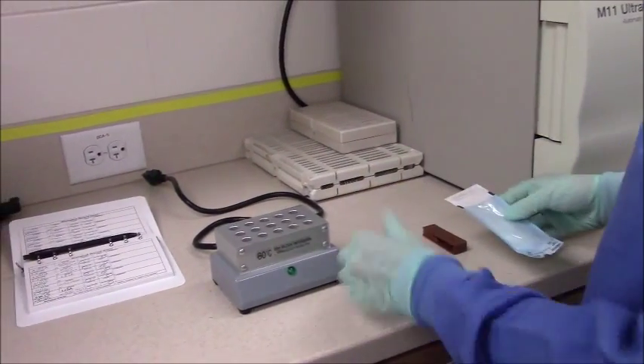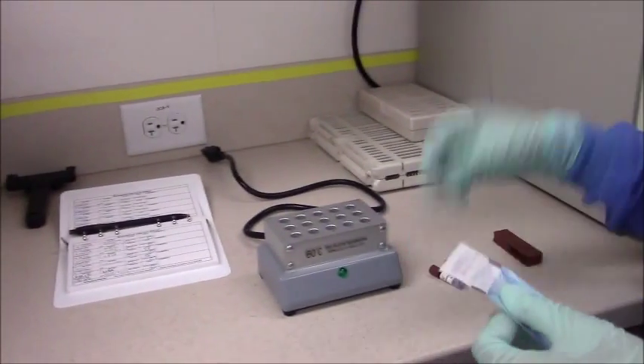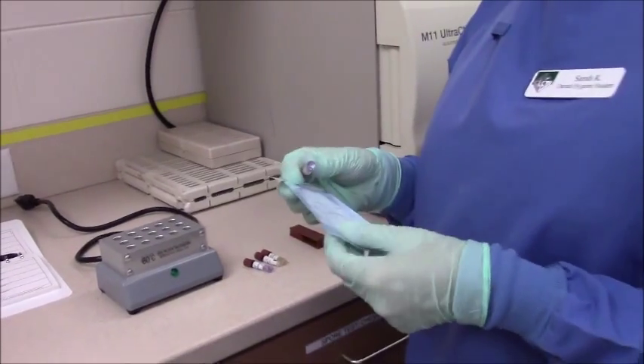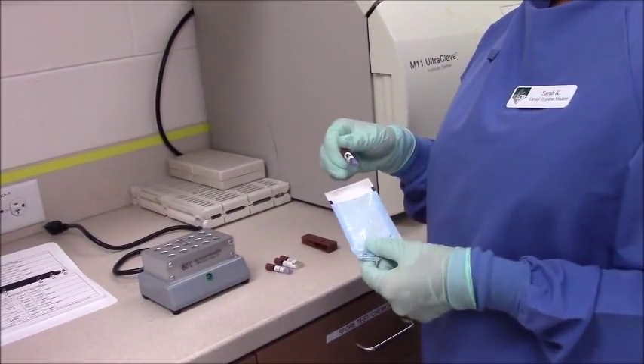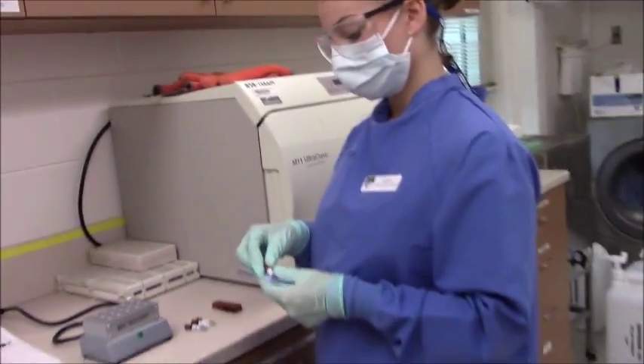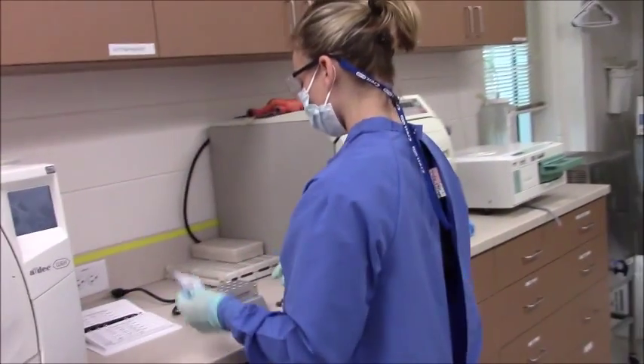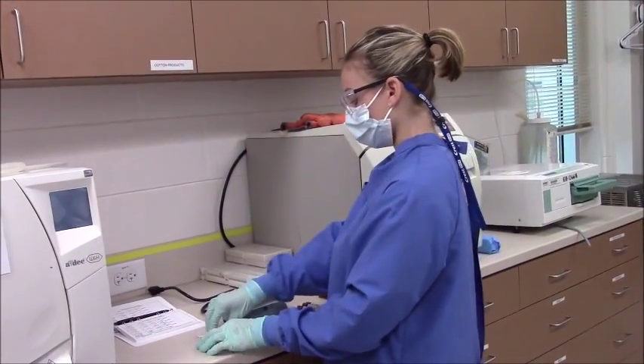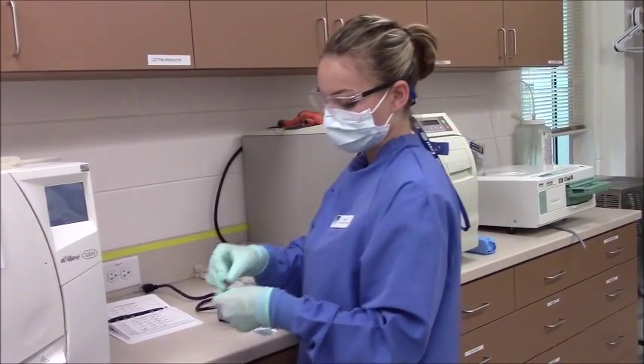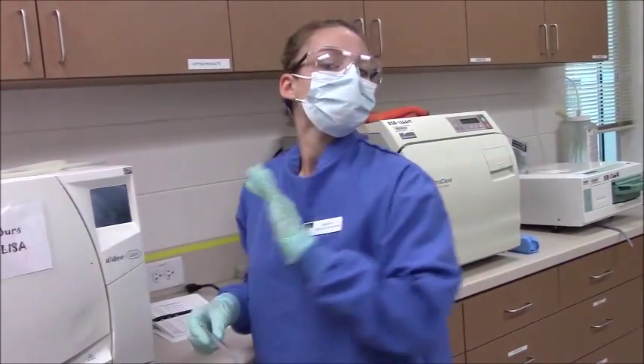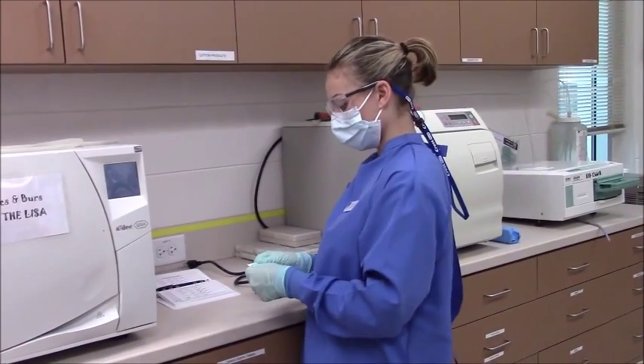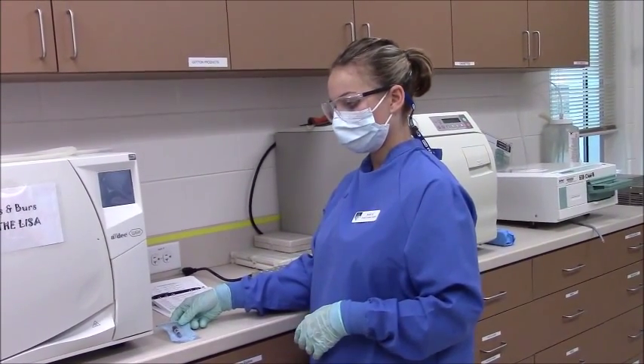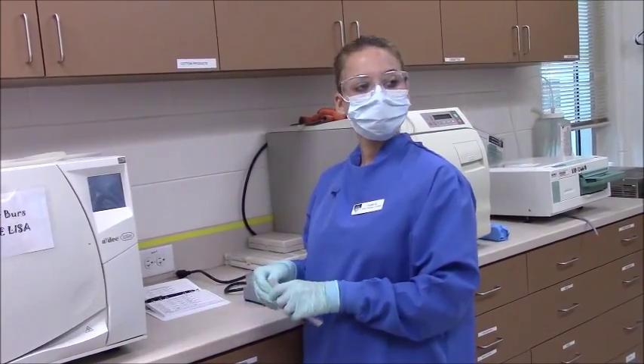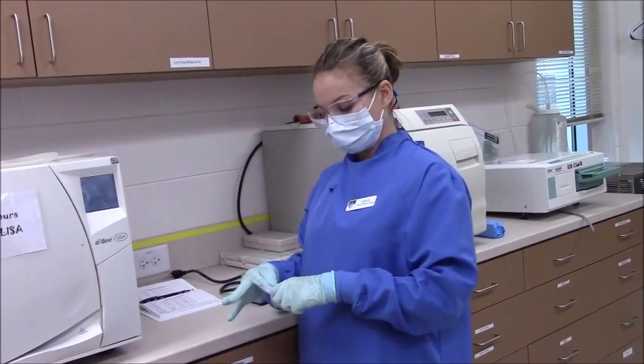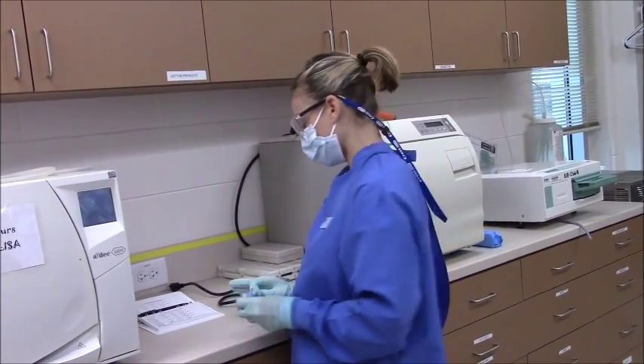Spore testing should be done weekly on each sterilizer. Use a spore capsule to test each sterilizer. Label one capsule for each sterilizer: autoclave, Statim, and Lisa. Place the capsules in a small sterilization bag, seal, and place in the appropriate sterilizer. Run each load as normal, adding the appropriate capsule label to the front of the load. When the load has completed its cycle, wait for it to cool for 10 minutes, and then crush the middle of the capsule.